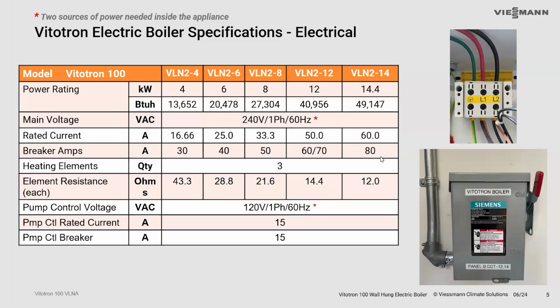These are staged units as well. We'll have a look at how many elements are in these units, and they're not just full on at that output. We can stage those elements as we move through here. So they are a bit of a reset boiler as far as turn down goes, being an electric boiler. Voltage is 240 volts, that's your incoming power for the elements itself.